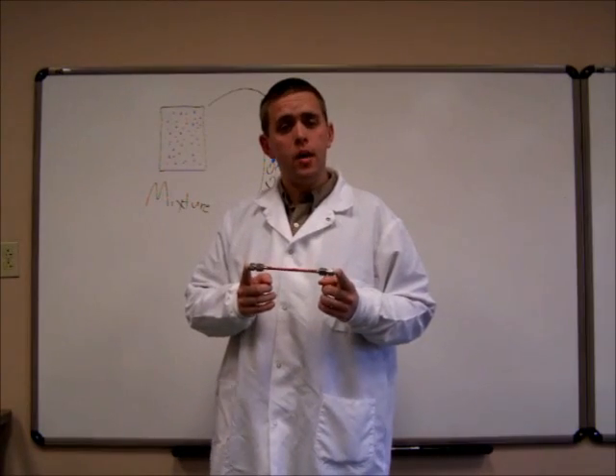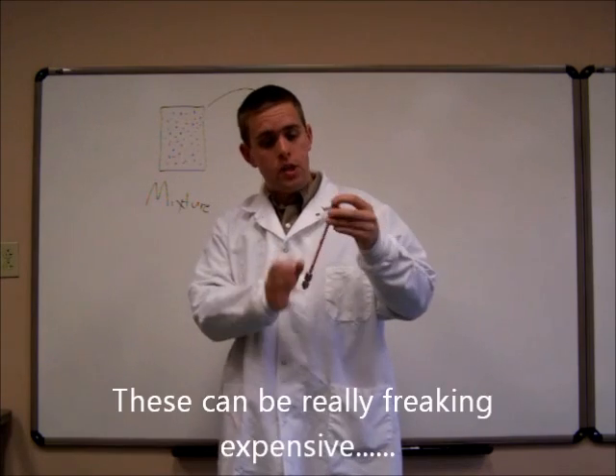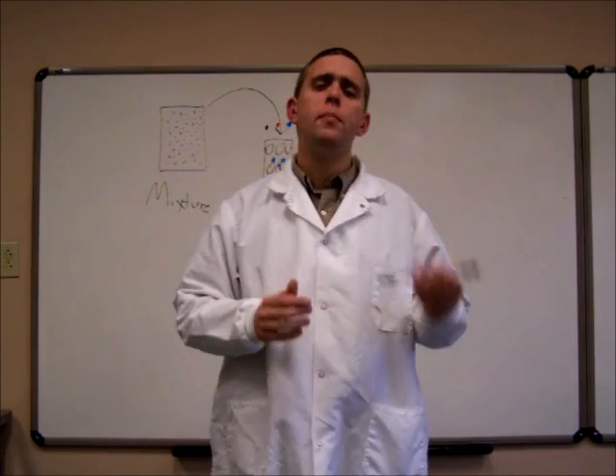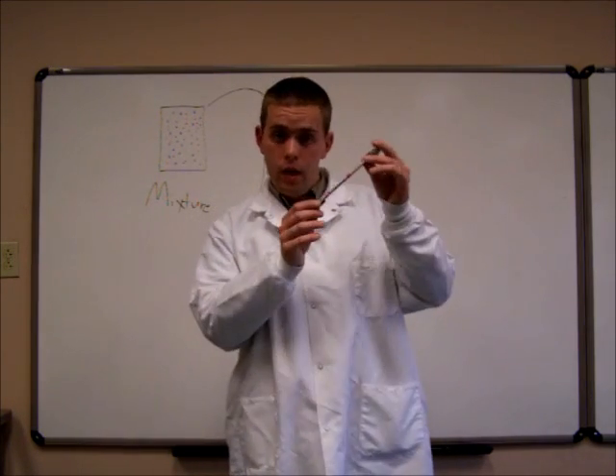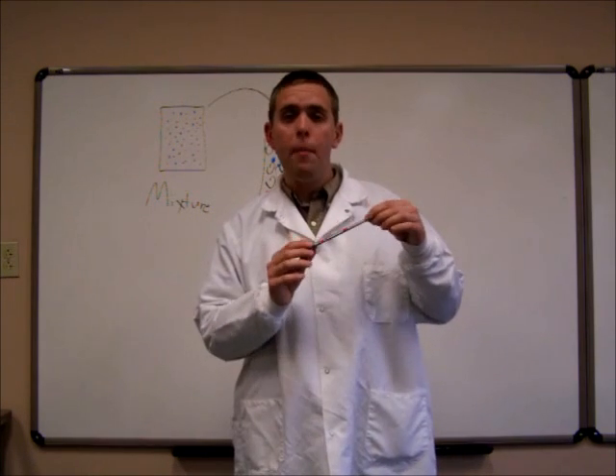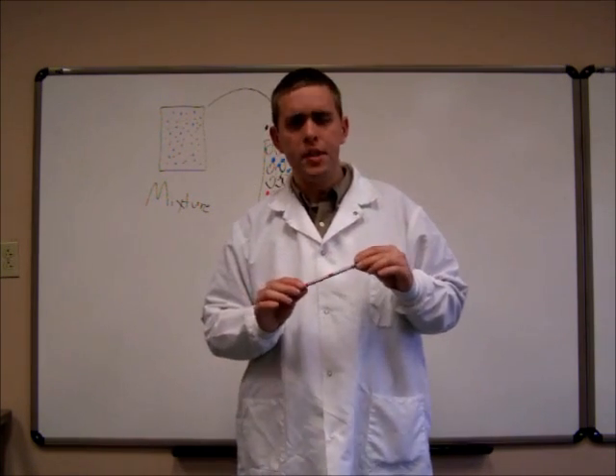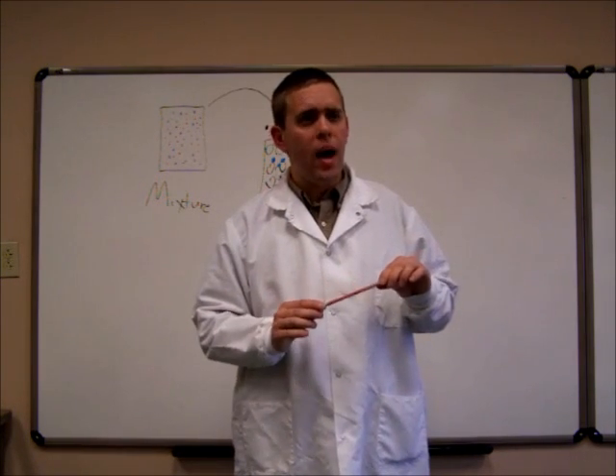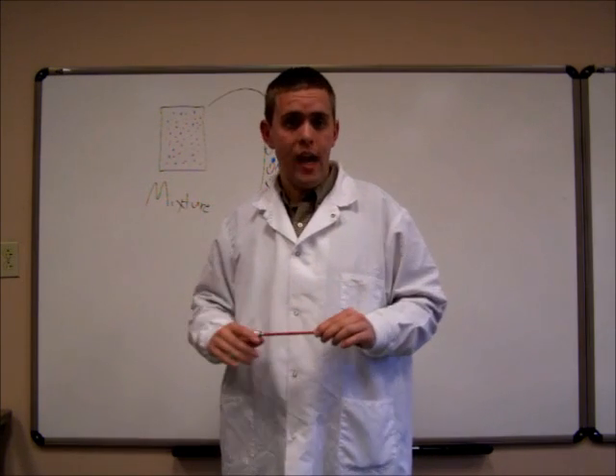For HPLC, we use this form of chromatography column. It's a long column, silica packed, that the analyte travels through. Now different projects are going to require different sorts of columns. This here is a much longer column. Compounds going through it, the mobile phase going through it is going to have more time to separate. So as it's being analyzed, it will not only take longer, but it will give a more clear indication of which chemicals are eluting at different times.